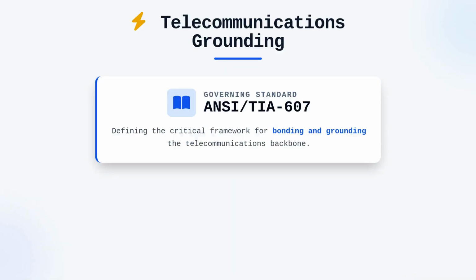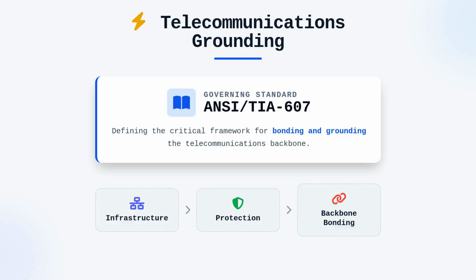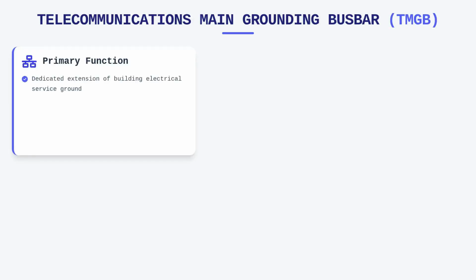Welcome back. Let's get into the specifics of telecommunications grounding infrastructure and how the ANSI TIA 607 standard defines the backbone. The Telecommunications Main Grounding Busbar, or TMGB, functions as the dedicated extension of the building's electrical service ground to the telecommunications infrastructure. Its primary purpose as a central attachment point is to consolidate all bonding conductors within a facility to ensure a common potential across the system, effectively mitigating ground loops and transient voltage surges.